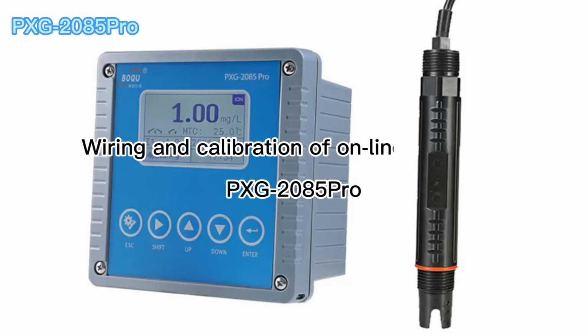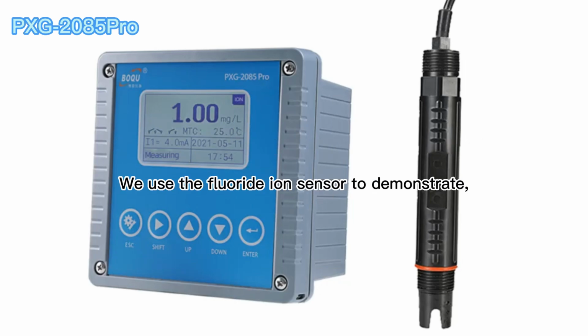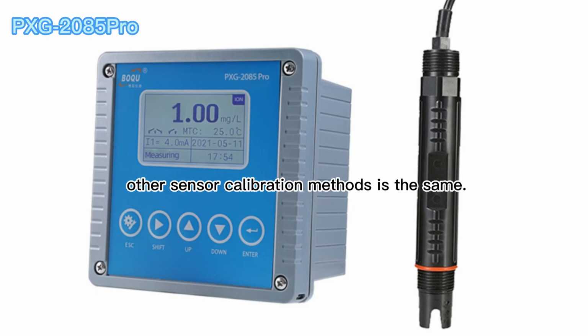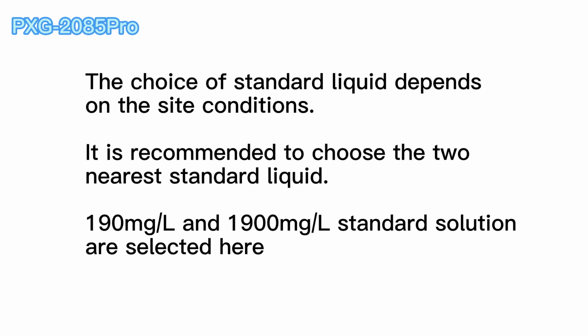Wiring and calibration of online ion meter. We use the fluoride ion sensor to demonstrate. Other sensor calibration methods are the same. The choice of standard liquid depends on the site conditions. It is recommended to choose the two nearest standard liquids. 190 and 1900 mg per liter standard solutions are selected here.